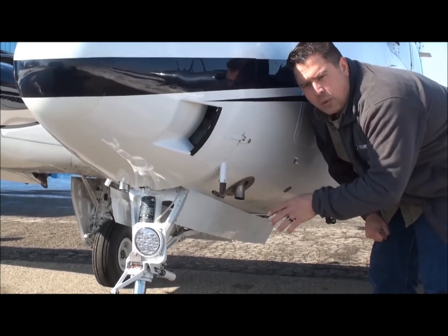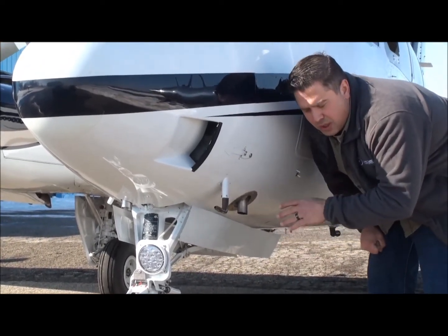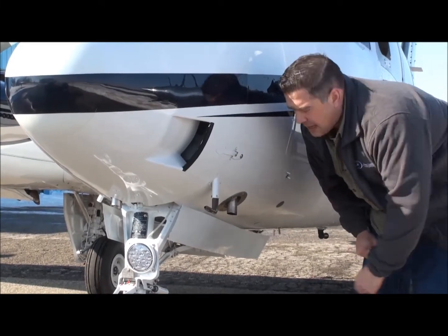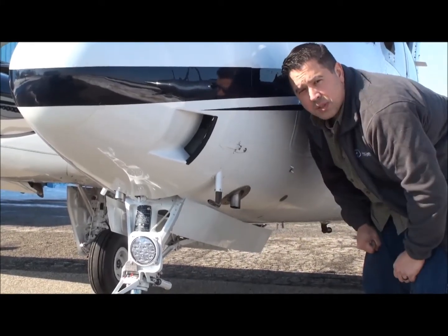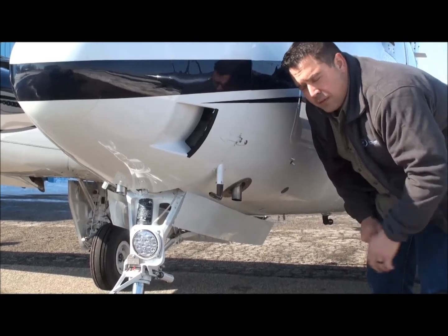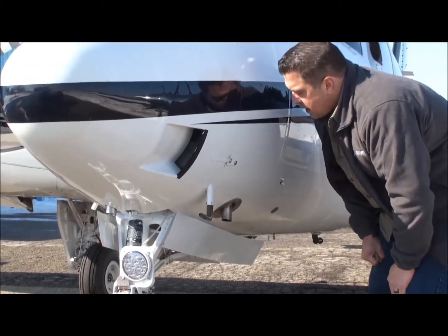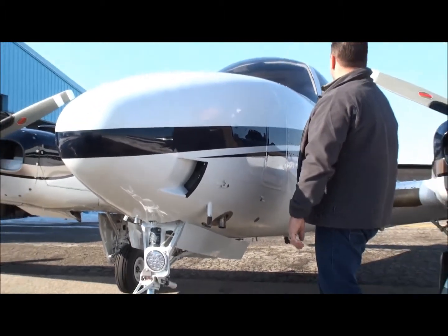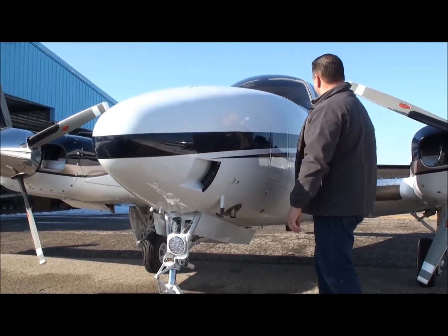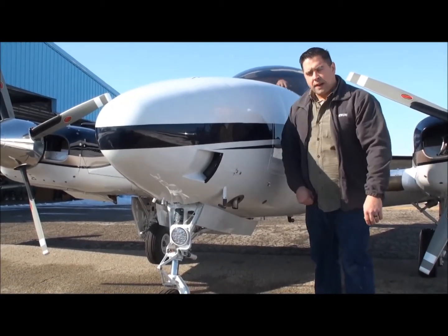You have to be very careful while doing this, because it's possible you could make the heater ignite while you're down here playing with the exhaust pipe airflows. So just be careful, keep that in mind. Now the other thing is we're going to turn it to medium heat. In this instance the heater fired off.